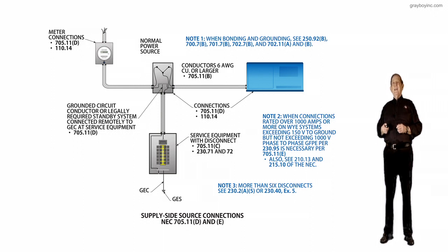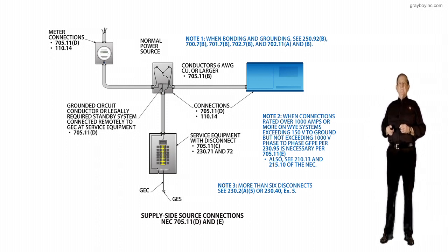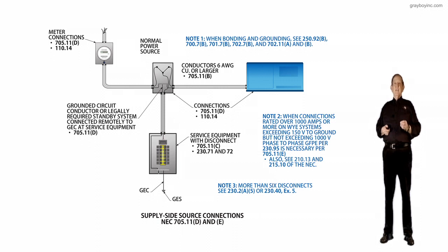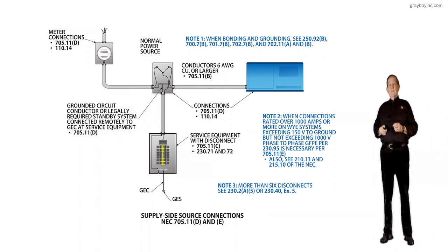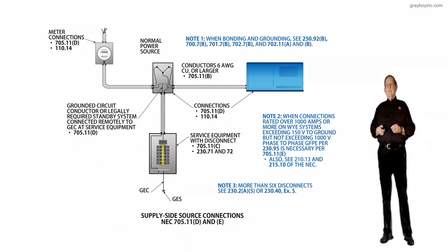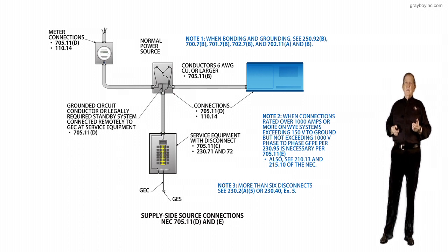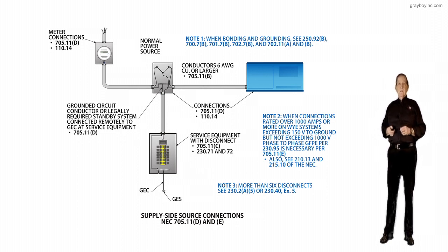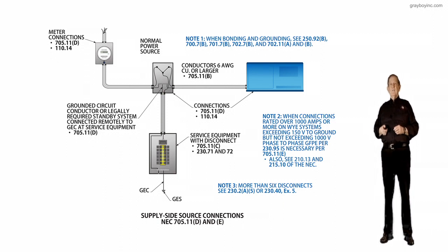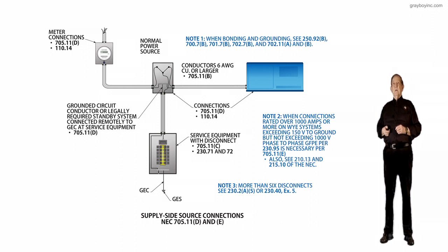And then if it's a single main like you see there in the panel board, which it has to be by 230.71(B) as in boy, then we would review 230.70(B) and 230.71(B) as in boy. And then if you had two to six disconnects, you would review 230.71, which allows 2 to 6 individual enclosures. And you could also review 230.72, which states they have to be grouped. But notice in this panel board, as you see there, we have to have a main ahead of it. We couldn't have just six individual mains in there like the previous code would allow you to maybe have.